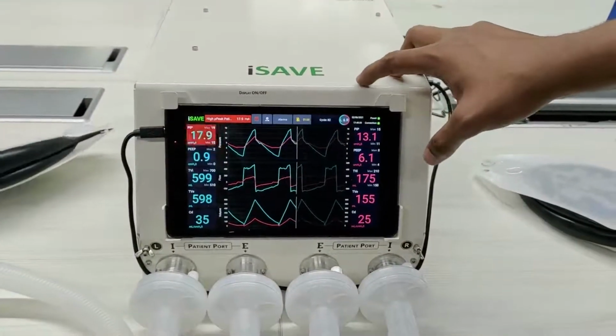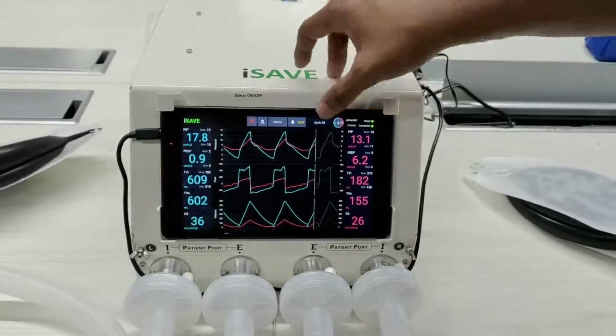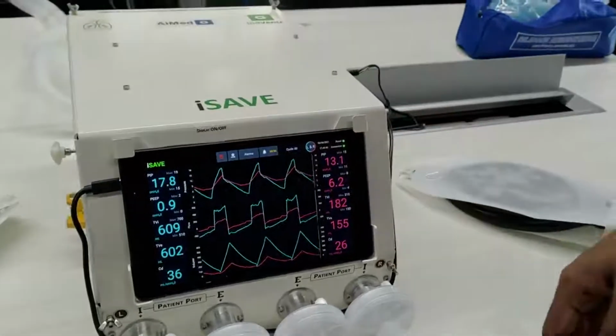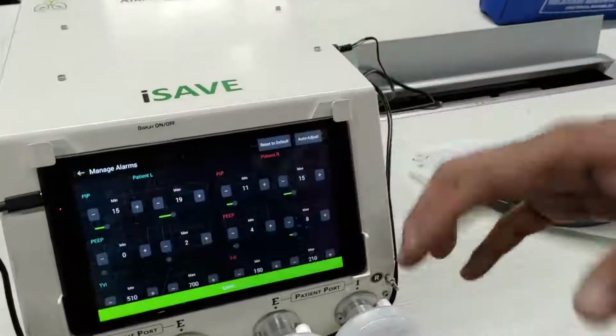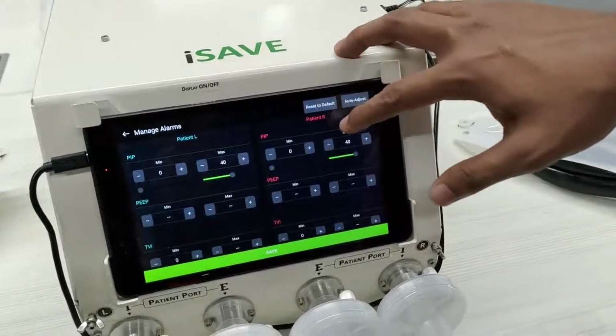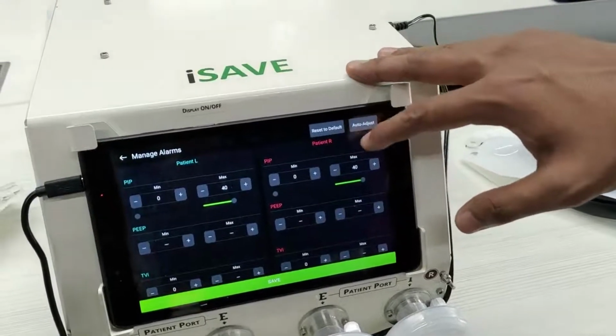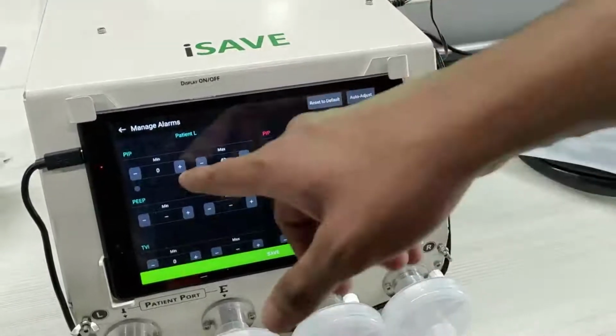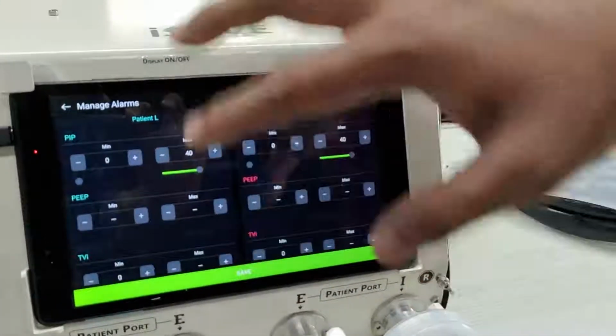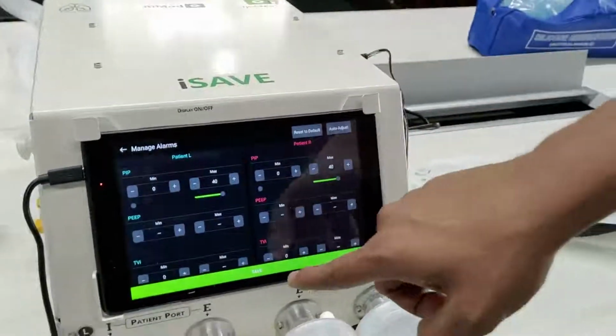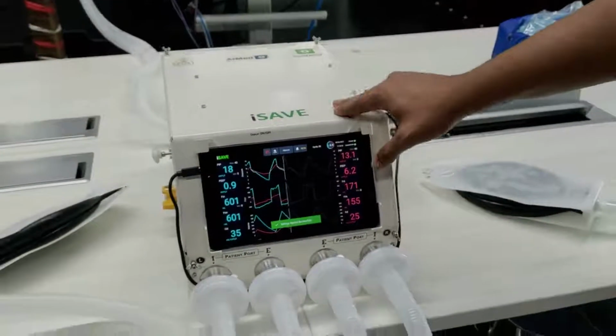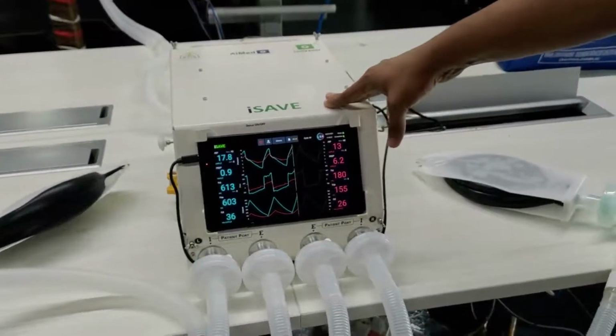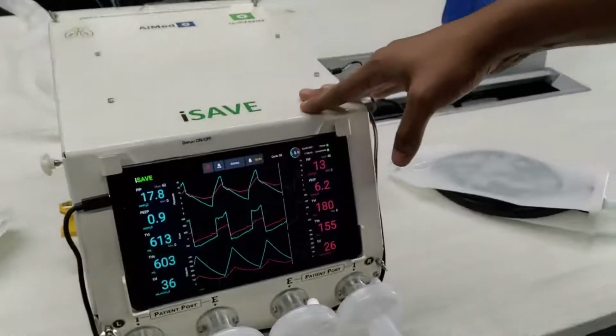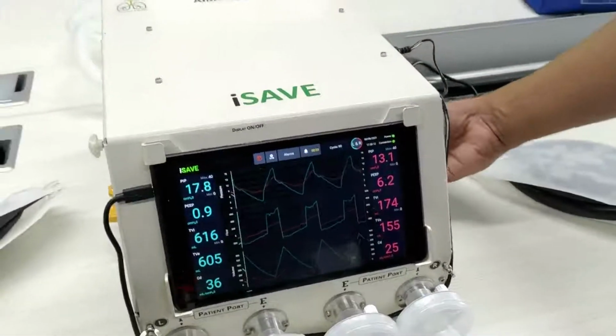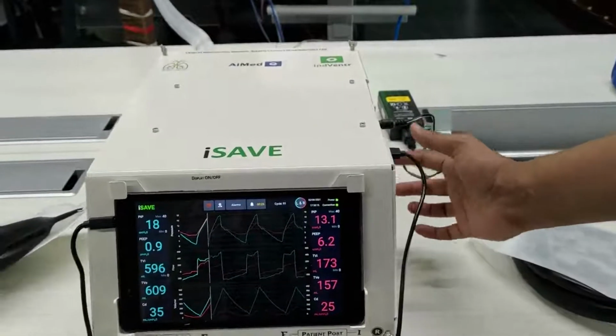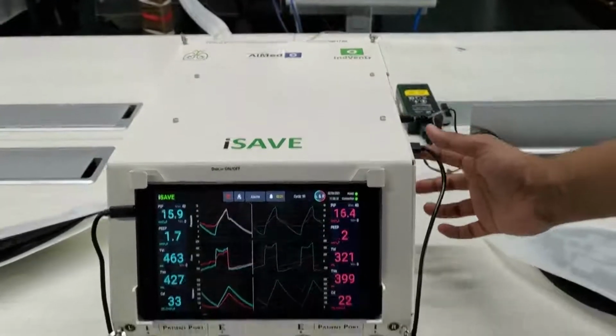You can see that these alarms are pretty much going away because they're within the margin. Similarly, if we don't know what we want, we can just reset. We can auto adjust if we don't know what we want, or we can reset to default, and that'll just make sure that the peak inspiratory pressure is within safe range. Okay, let's save those settings. So this is volume control mode on the ventilator. So let's reset all of our PEEPs, and let's also test out pressure control mode.